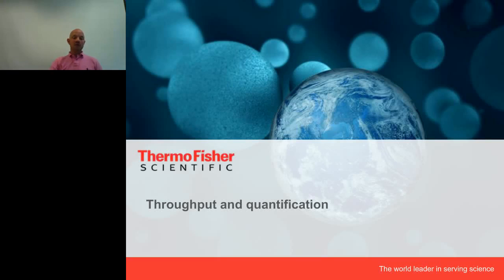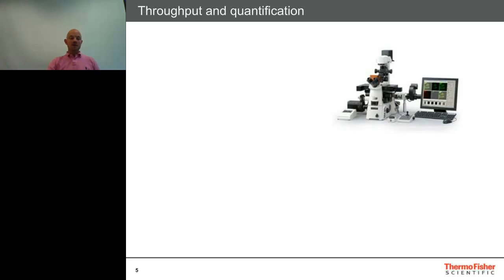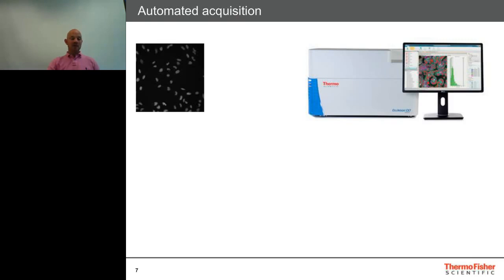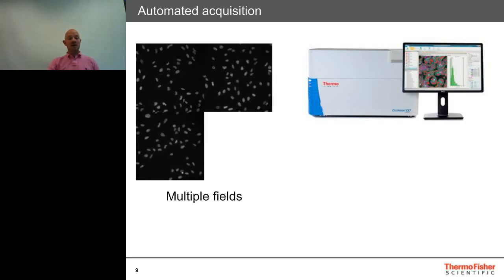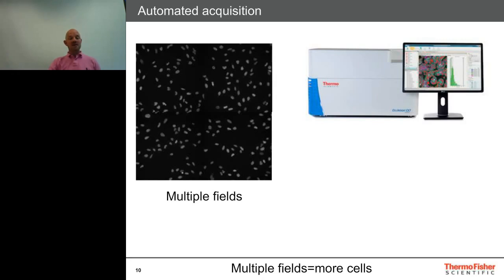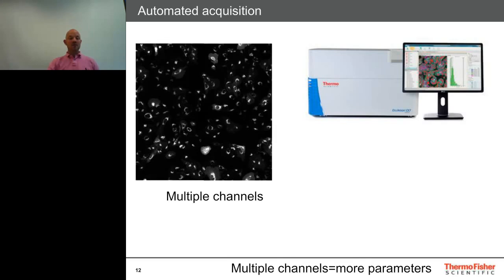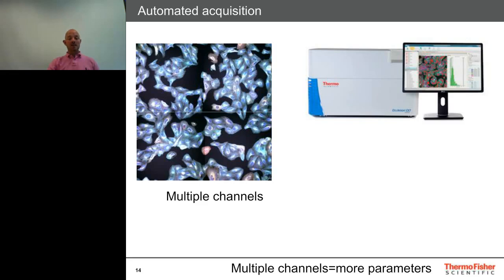So how do we address those drawbacks of throughput and quantification? We're starting with essentially a regular fluorescence microscope, but we package it up in a box. With high content imaging and analysis, we don't just stop at one image — the system takes another field and another and another. This automated acquisition allows us to gather a large number of cells from a very short imaging protocol. Using multiple emission filters, we can get many channels and build up an in-depth picture of the spatial and temporal distribution of molecules within cells.